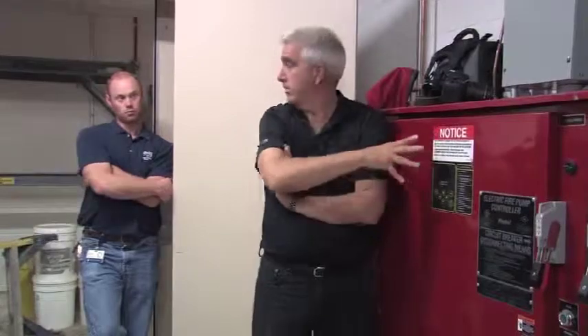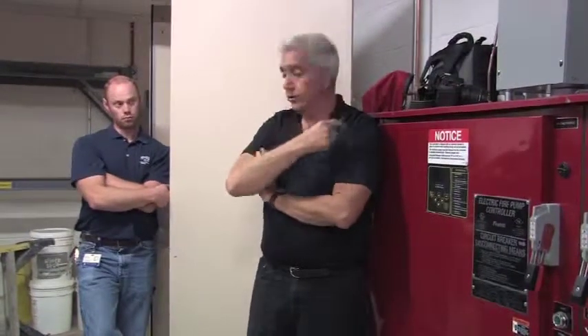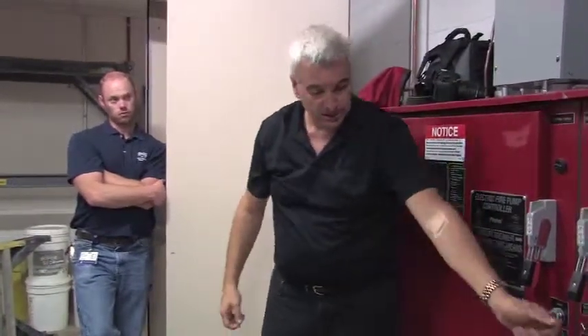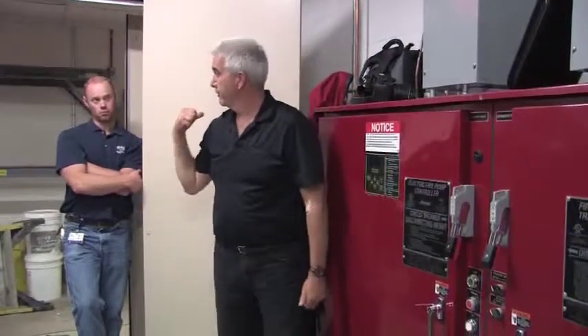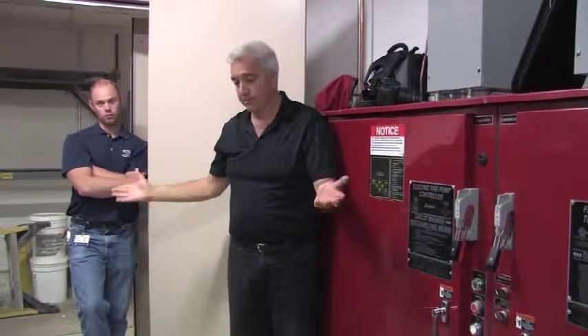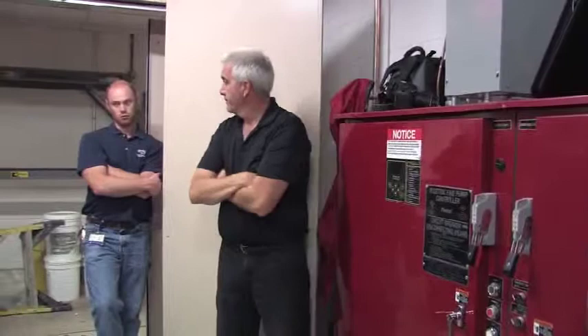Annually, you obviously do a full flow test every year, and transfer over the generator. The best way I check a transfer function is to start with the main power from outside the controller. You can shut it off here, or you can use these selector switches, but I prefer to have somebody put the main switch to simulate a power outage. That's what we really do. We open up the main feeder breaker and let it just fire up.